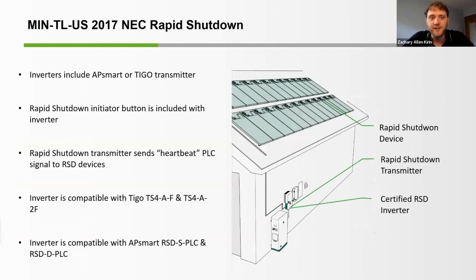So the inverter features rapid shutdown compliance. Again, this could be either with an AP Smart or a TIGO transmitter built inside the inverter, depending on the device you order. A rapid shutdown initiator button is also included with the inverter. This is something that is just plugged into the inverter and allows for an emergency stop and a rapid shutdown initiation.